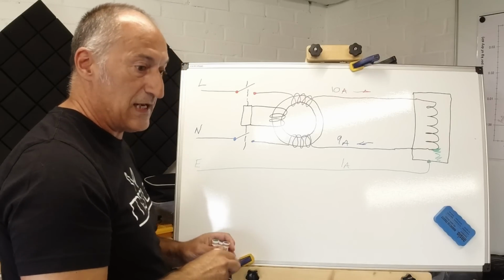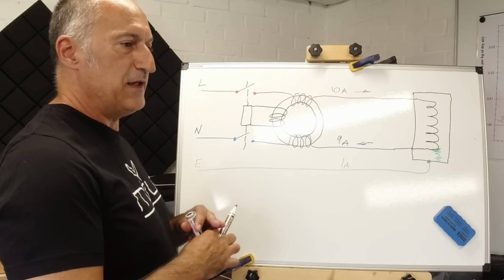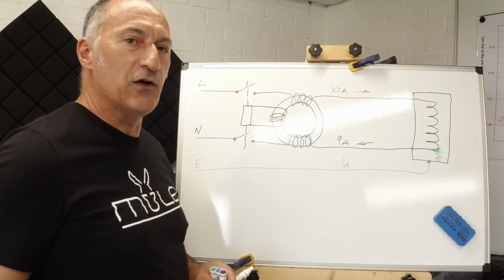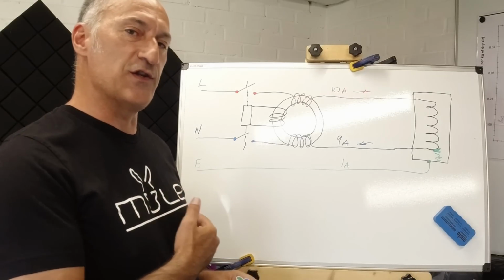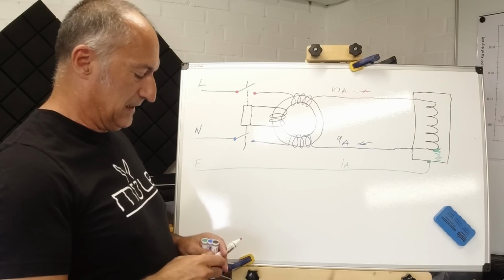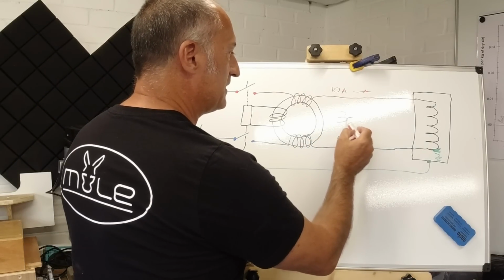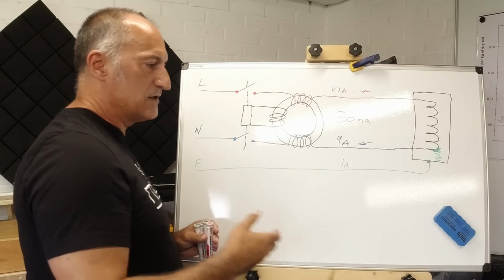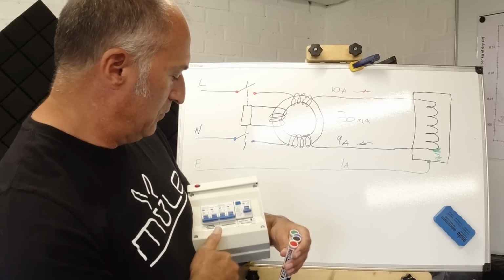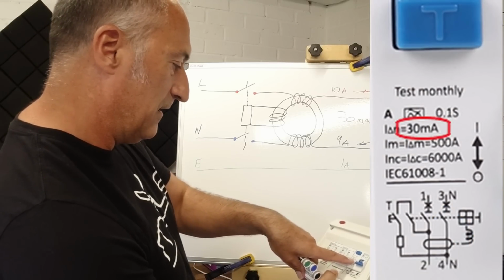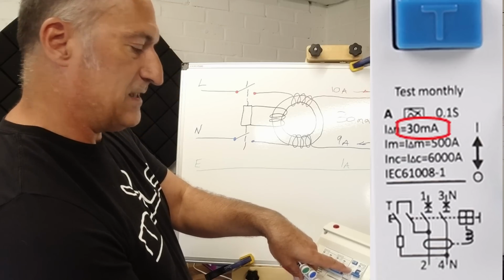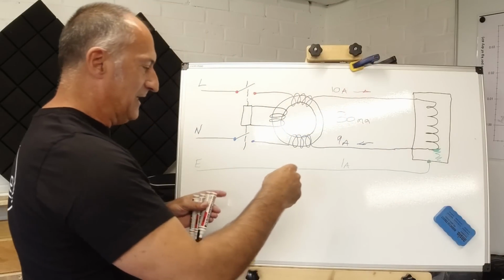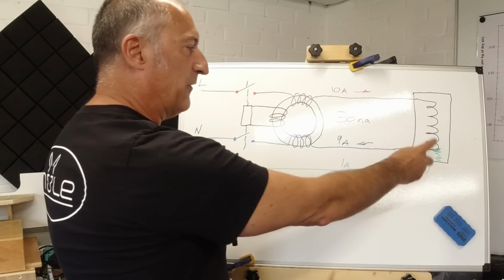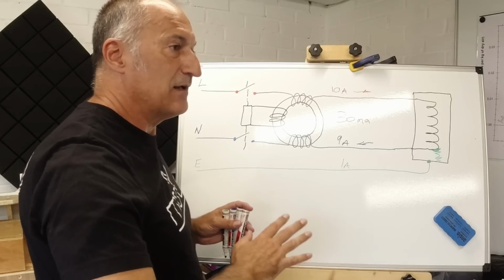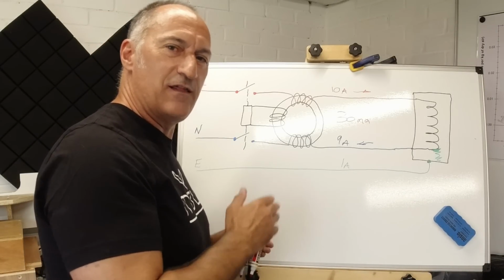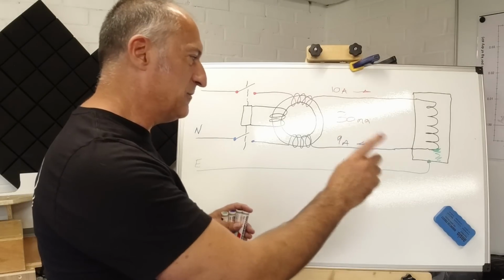Now the human body can only withstand a very small amount of current, something in the region of 50 milliamps. Anything above that could be fatal as a shock across the body and across the heart. So an RCD needs to have a rating of less than 30 milliamps, and most of the ones that you'll see, certainly the ones that I shall recommend that you purchase, when you look on the actual RCD in the small writing on the front, I can clearly see here that this one is rated for 30 milliamps. So when you've only got literally 30 thousandths of an amp flowing to fault, that RCD will trip. And in fact, typically they normally trip anywhere between 15 milliamps and 30 milliamps. So it's a really small amount of current that it will detect.